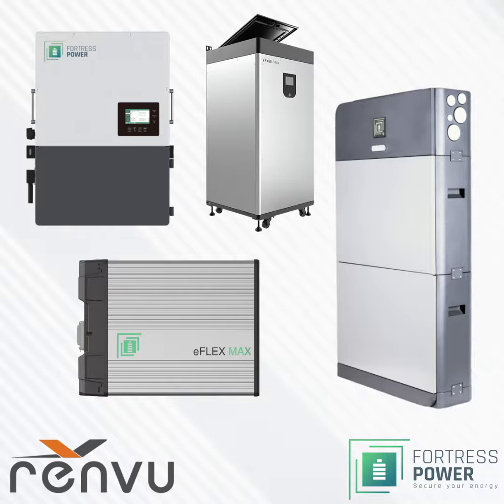What really sets this eFLEX product apart for me is the E-Way. It's ultimately a built-in wire management system. There's a 750 amp bus bar built into this E-Way that stacks right on top of the battery. For a lot of the installers on here, when you've had to do those gutters, some of those gutters are huge. It costs time, it costs material. It eliminates the need for a gutter. 750 amp bus bar built in. There's knockouts on each side, and there's a knockout on the top of it that allows for the RENVU inverter to stack right on top. It seals right on top.